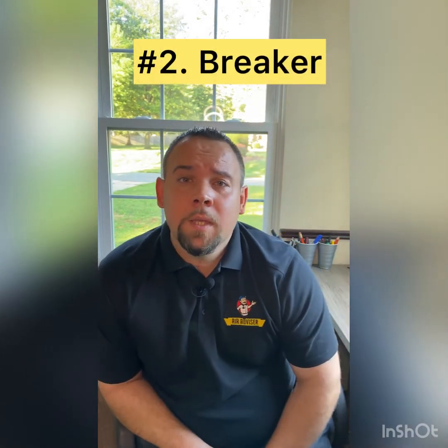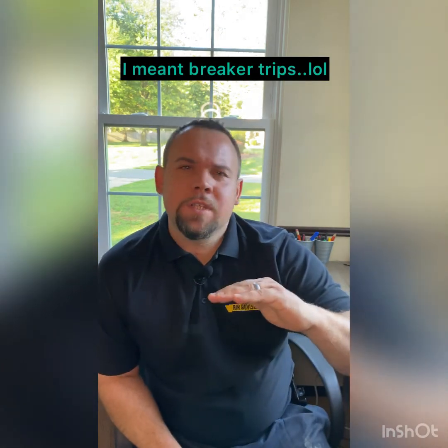Next really simple thing is you're going to want to go to your breaker panel and check the breakers. I know this sounds really simple and you're thinking it's very easy to see if there's a breaker that's off, but actually it can get a little bit tricky. Most times when a breaker trips, it doesn't completely trip. It'll just partially trip to kill power. So you're going to have to actually find the AC breaker, physically turn it all the way off, and then physically turn it all the way back on.